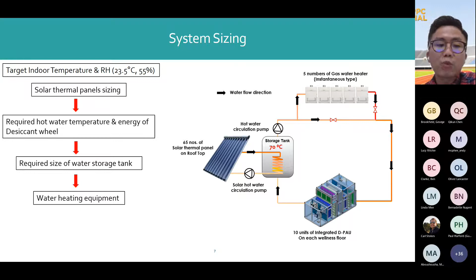Then I coordinated with the desiccant wheel supplier in order to find the suitable dimension and also the required hot water temperature for the desiccant wheel regeneration process. Then I could size the volume of the water storage tank based on the total output power of the solar thermal panels and the required hot water temperature of the desiccant wheel regeneration. 5 condensing instantaneous gas water heaters were installed to maintain the hot water temperature, even if the output power of the solar thermal panels is not enough.